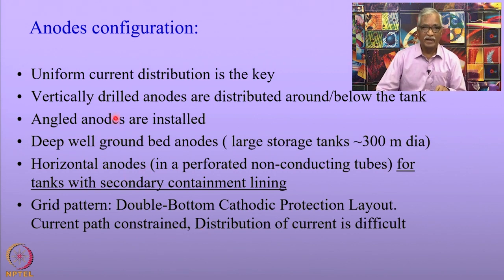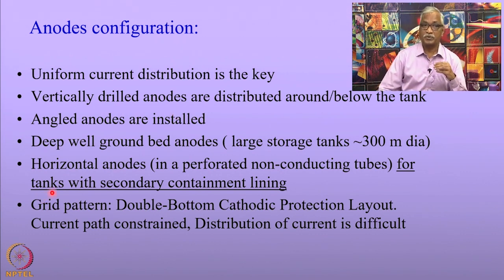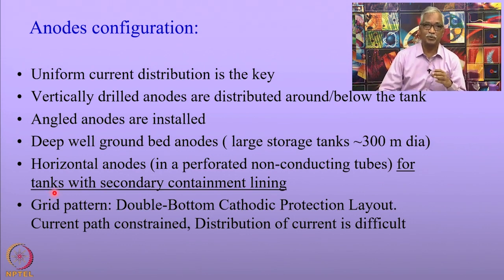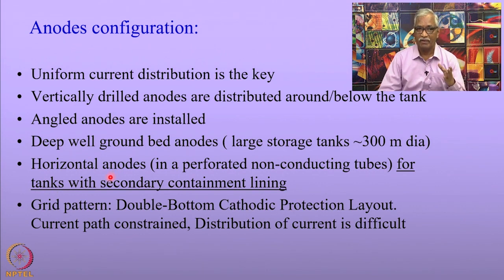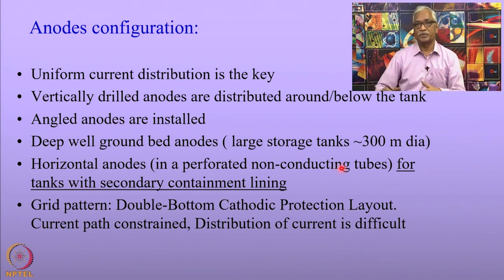We can also have vertically drilled anodes distributed around the tanks so that the current is uniformly distributed, or we can have angled anodes which give even better distribution of current. Where distributed anodes cannot be used, deep well ground bed anodes can be installed for large storage tanks of around 300 meter diameter.